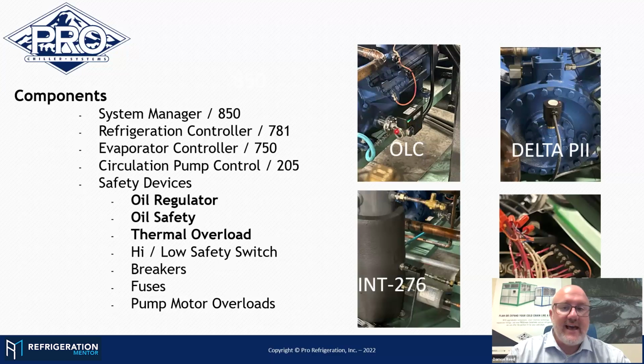The oil regulator does have a little float that extends into the crankcase of the compressor. It makes a decision on whether it needs to let more oil in and keep the oil balanced. If you've got a good oil level in the sight glass and your float's happy, your oil switch should be happy. Green is good. We also monitor the oil pump side of the compressor. That's just a Delta P2 differential oil pressure control. So it's monitoring, hey, when this compressor's running and it starts, I need to start looking at net oil pressure. And is my net oil pressure good enough to stay running, or is it not?